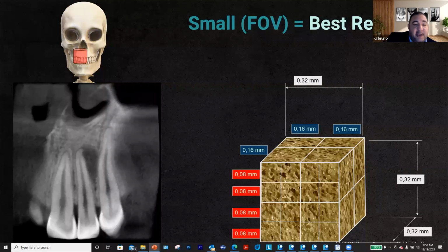So Dr. Arai said that 0.08 is the smallest you can go without detriment to the image quality. That's why Morita keeps 0.08. So if another manufacturer tells you, oh, I have a smaller voxel size, therefore I have higher resolution, it's nonsense. It doesn't make any sense. It does not increase resolution whatsoever. They actually shoot themselves in the foot, and I'm going to show you why in a second.